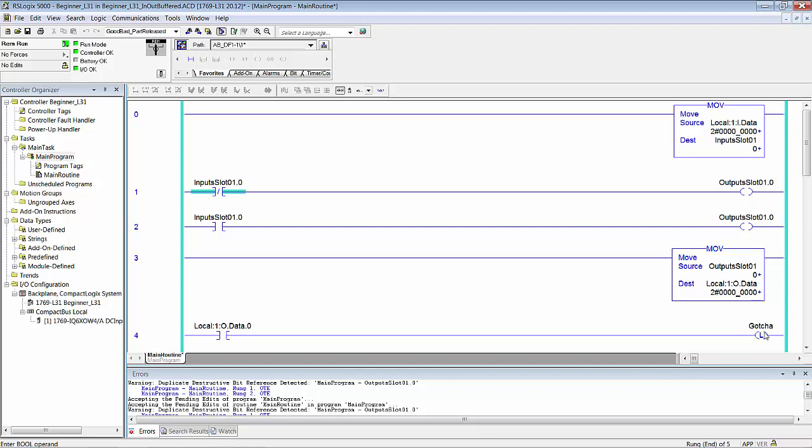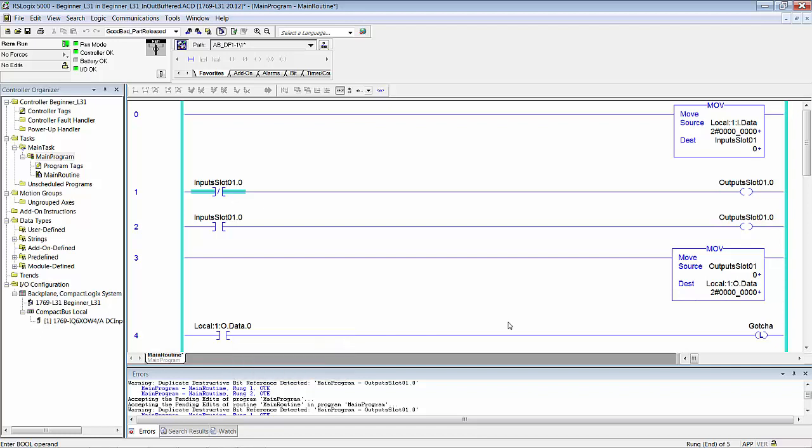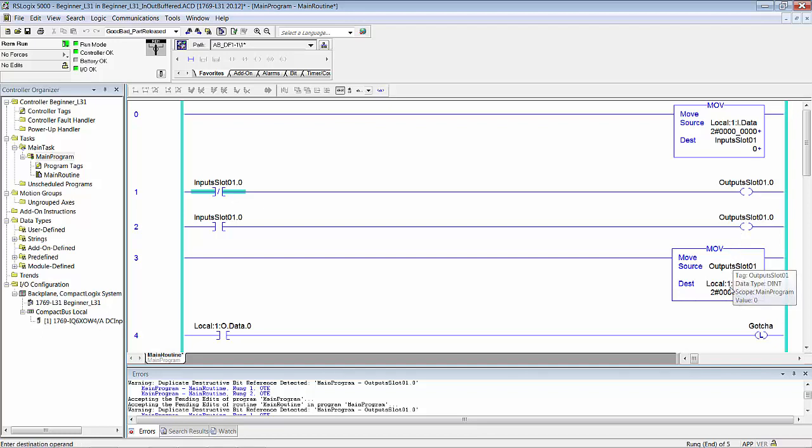But if I look at the buffer data, that's not going on. Just because you see it go on here doesn't mean that that bit of this word got transferred to this word. So remember I told you that the screen hooked to the video display hardware in my laptop through the chipset, through the USB port, through the USB to 232 converter to the 232 port on that L31. There's no way in the world that that string of electronics could ever keep up with the rate of change in that processor. It's just not possible. What you're seeing here—this is really interesting, this is a freebie. You see this bit going on in memory because it is going on.